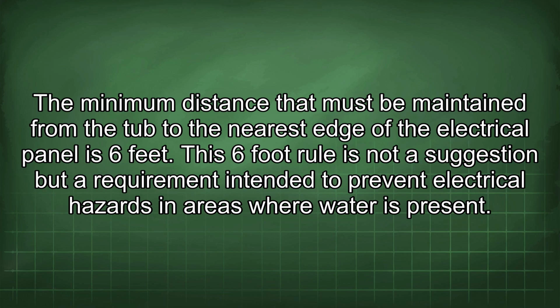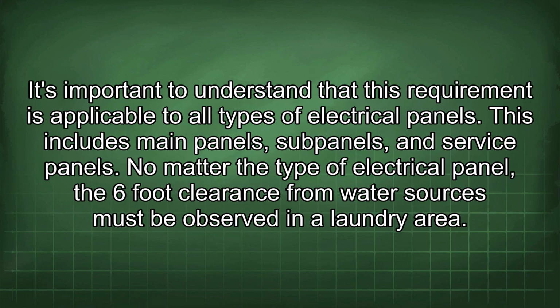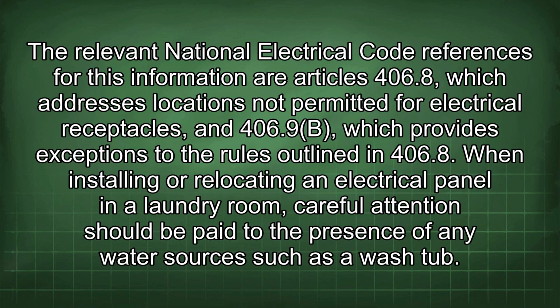It's important to understand that this requirement is applicable to all types of electrical panels. This includes main panels, subpanels, and service panels. No matter the type of electrical panel, the 6-foot clearance from water sources must be observed in a laundry area. The relevant National Electrical Code references for this information are Articles 406.8, which addresses locations not permitted for electrical receptacles, and 406.9b, which provides exceptions to the rules outlined in 406.8.